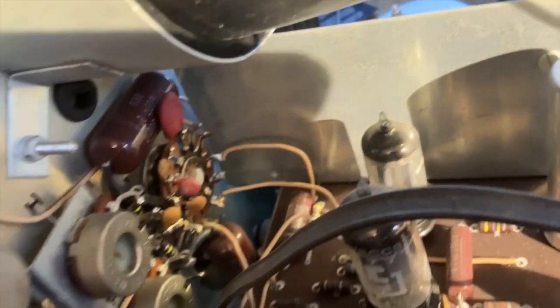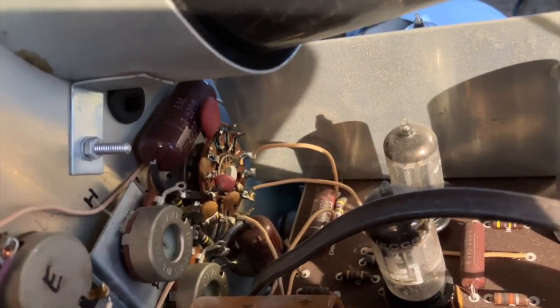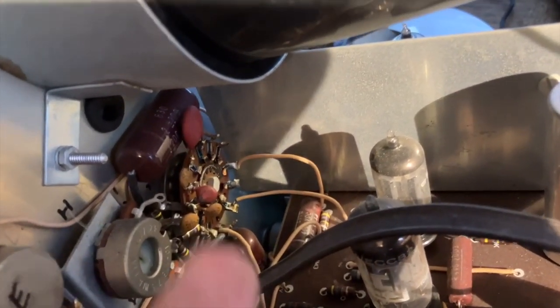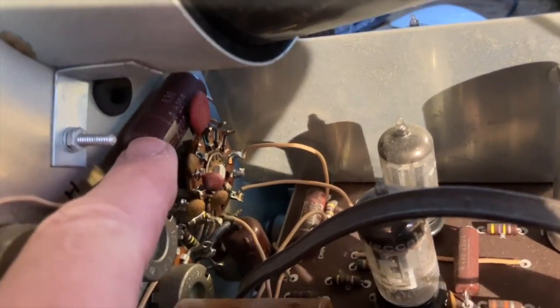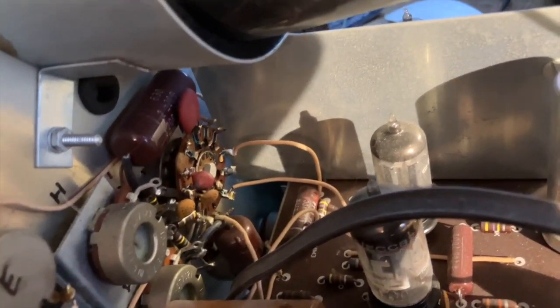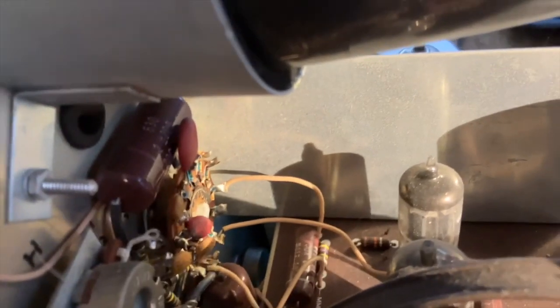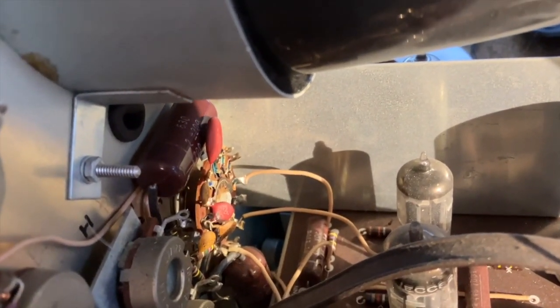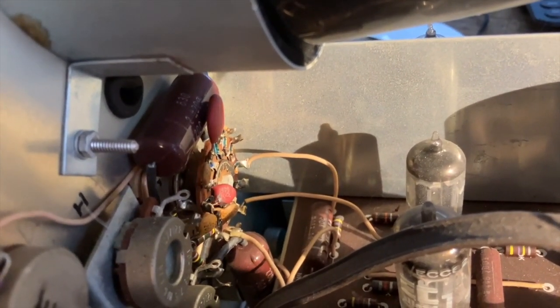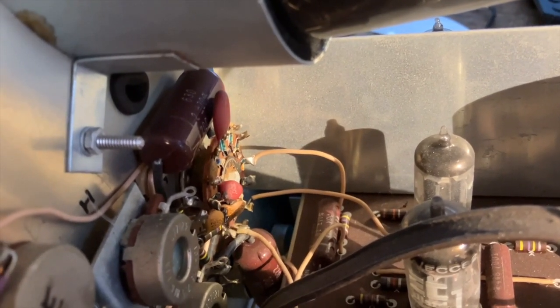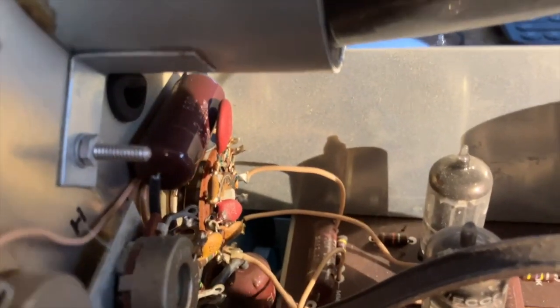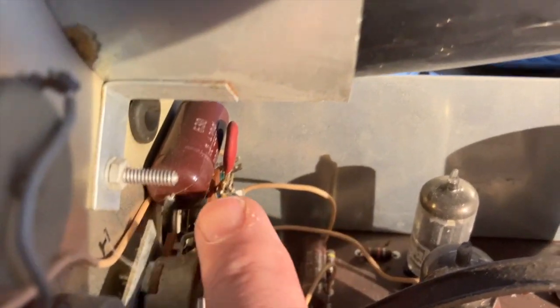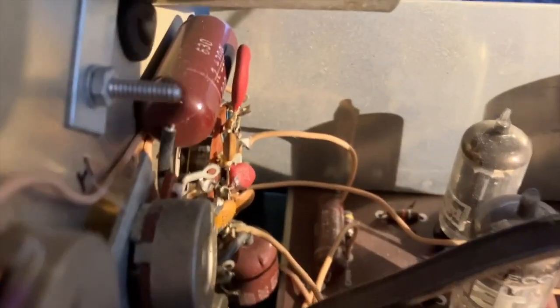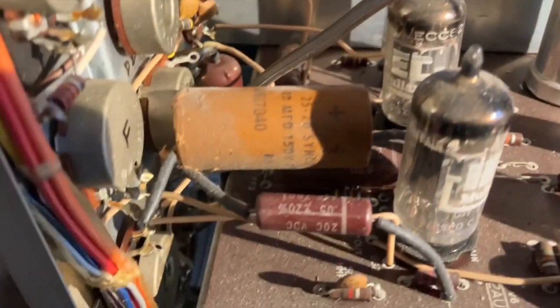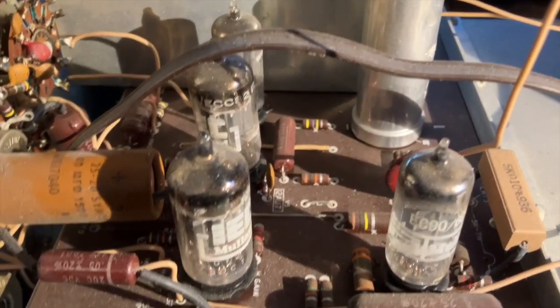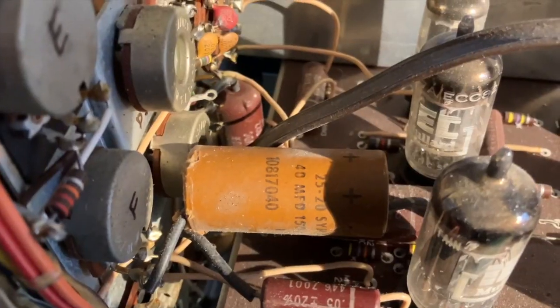The main frequency selector switch here is switching in a bunch of different caps, and in particular the lowest frequency one is this 0.2 here, and I think I'm going to replace it because I noticed some nonlinearity when showing multiple cycles of 60 hertz at the lowest frequency, and that's typically, I found, when it's time to replace this guy. Apart from that, this is the sweep area, the sweep generation area, of course.